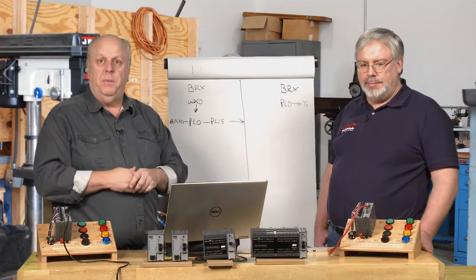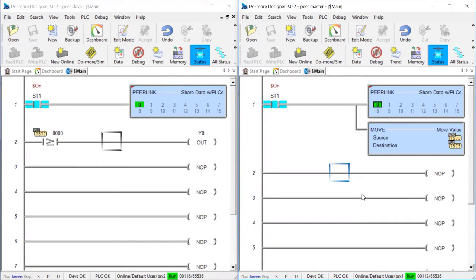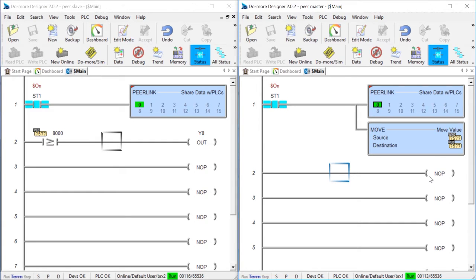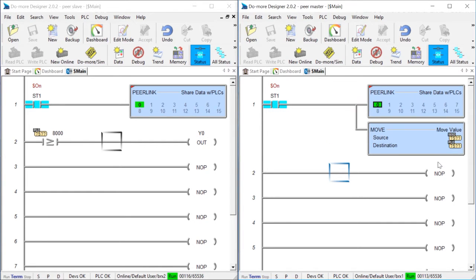So what I did over here—and you'll see it here in the ladder code—I put my PeerLink block in. I move WX0, which is the analog raw value coming off the card, over to PL0. That's all I did. Then 10 times per second, PL0 is published out to the network. Then over in this PLC, it shows up as PL0.